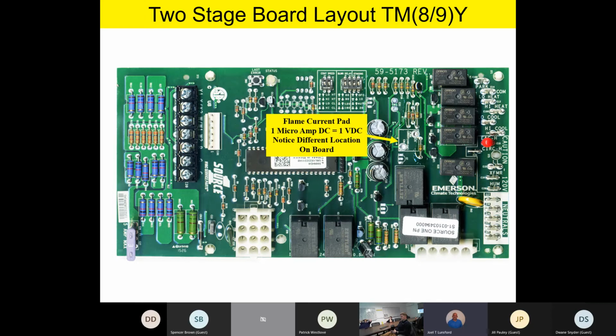About in the middle of the board, towards the right-hand middle side, is our flame current pad. Now, team, if you recall from our last training session, you'd notice that the flame current pad was at the bottom of the board. So please notice that on this particular board, the flame current pad does the exact same thing. If you take your voltmeter and go between those contact points on the flame current pad, with your voltmeter set to DC volts, you can actually read flame current on that pad, but it will come out as voltage DC.